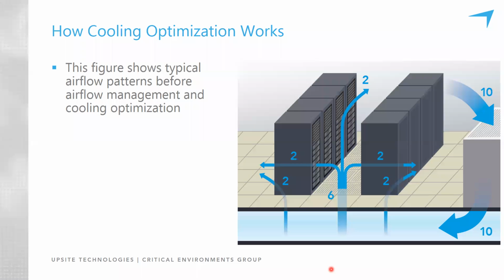In the following images, we have a simple room with 1 cooling unit and 2 rows of cabinets. These could represent a large room with many cooling units and many rows of cabinets. The concepts and the ratios of the airflows all still apply. In this room, we have a total of 10 units of air moving through the cooling units. That's generally referred to as CFM, cubic feet per minute. So we've got, say, 10 CFM, 10 units of air moving through all the cooling units. If you add up all the air coming out of all the openings in the raised floor, it will be a total of 10. In this example, we have 2 units of air coming out of unsealed cable openings under 1 row and 2 units of air coming out of unsealed cable openings in the other row, and then 6 units of air coming out of supply tiles in the cold aisles, for a total of 10.